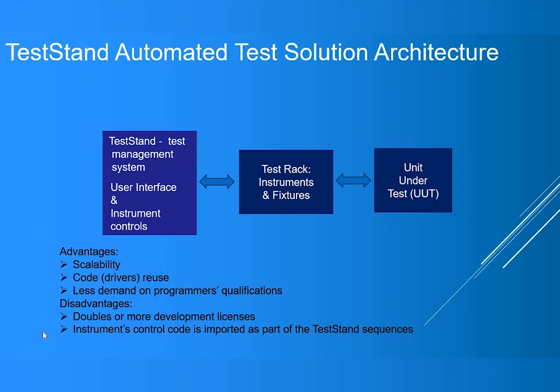TestStand is the test management system, which performs user interface, instrument control, and report generation. Its advantages are scalability, better code or driver reuse, and much lower demand for programmers' qualifications. Disadvantages are: the test report is native to TestStand and difficult to customize, the user interface is not really user-friendly, and there is still a need for programmer involvement.